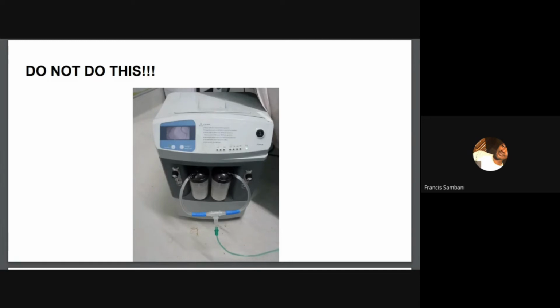So if it's a 5-liter oxygen concentrator, you're not supposed to test it at 3 liters per minute, but rather you're supposed to test it at 5 liters per minute. And if it's a 10-liter oxygen concentrator, you also test it at 10 liters per minute, not necessarily at 5 or 2, because it might perform at 2, but then it's not performing at the maximum rated flow. And you always want it to perform at the maximum rated flow, because that's how it's supposed to be.